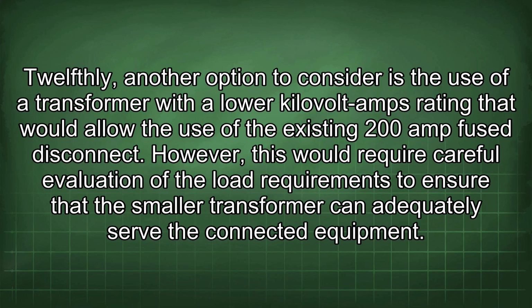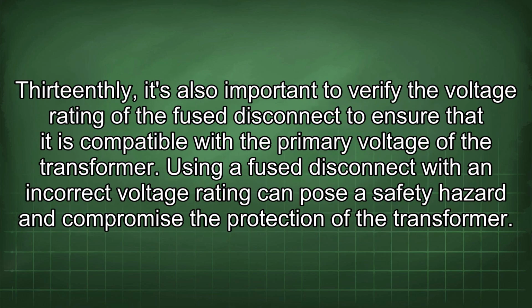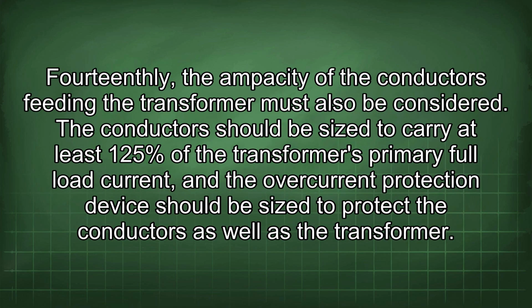However, this would require careful evaluation of the load requirements to ensure that the smaller transformer can adequately serve the connected equipment. 13thly, it's also important to verify the voltage rating of the fuse disconnect to ensure that it is compatible with the primary voltage of the transformer. Using a fuse disconnect with an incorrect voltage rating can pose a safety hazard and compromise the protection of the transformer. 14thly, the ampacity of the conductors feeding the transformer must also be considered.